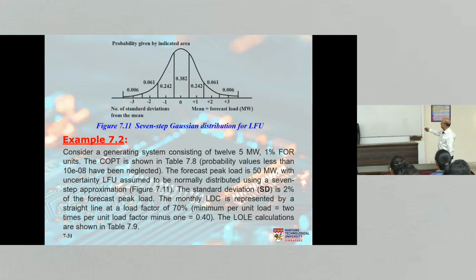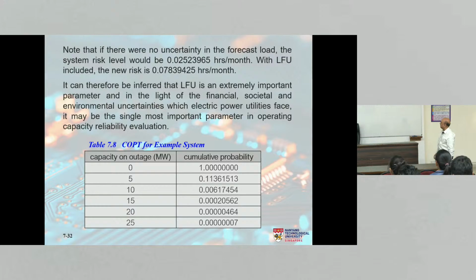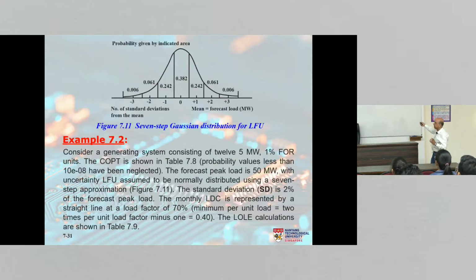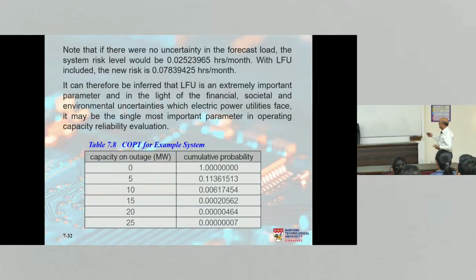in a straight line. The loss of load risk is what we are after. So if you do the calculations, you will find that at the mean value, what is the mean value of the load? The mean value of the load is 50 megawatt. At the mean value, which you can calculate, right? You have your capacity outage table using the binomial distribution, and if the peak load is 50, use the cumulative probability of 10 megawatt or more out of service, and you can get the loss of load expectation, right? So I haven't shown you that table, but you can determine that, and you will find that that is 0.0252396 hours per month, because the data is given for a month.